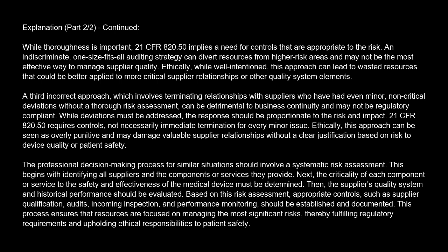The professional decision-making process for similar situations should involve a systematic risk assessment. This begins with identifying all suppliers and the components or services they provide. Next, the criticality of each component or service to the safety and effectiveness of the medical device must be determined. Then, the supplier's quality system and historical performance should be evaluated.